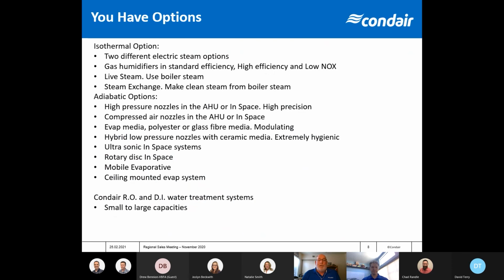And again, you have plenty of options here. With the electric, we have 2 different options for electric humidifiers. Gas humidifiers are available in standard efficiency, high efficiency, and low NOx. Live steam: use your boiler steam, or we'll make clean steam from the boiler steam. And then with the adiabatic options, high pressure goes into the air handler or directly into the space. Very high precision. We still have some compressed air nozzles around, but those are kind of going away. Air compressors are a big user of energy, so these are pretty much being replaced by high and low pressure pumps.